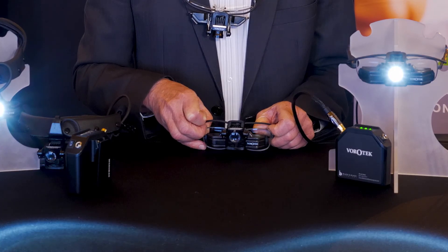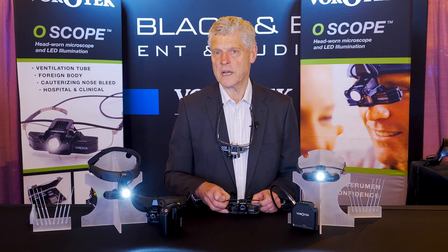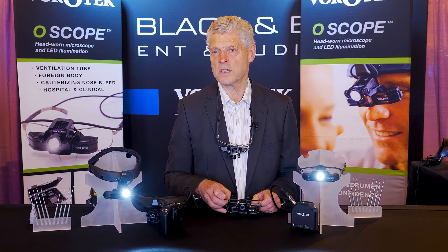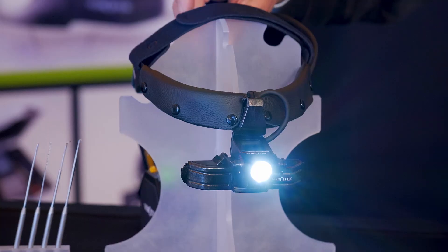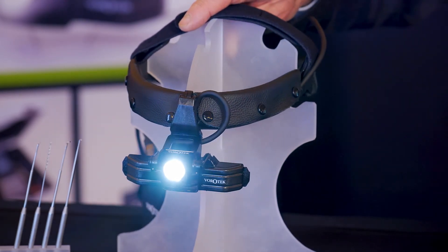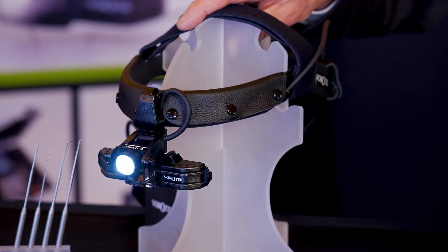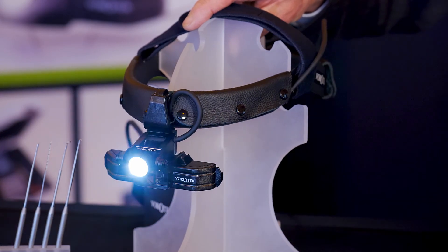It makes for a much more accurate and careful assessment. It is also very portable, so it's very easy to take it to other places in the hospital or anywhere else. Another appreciable advantage is the amount of time taken to perform examination and procedures — it is generally considerably quicker with an O-scope than with a microscope or a headlight. When there is any patient movement, a microscope will have to be repositioned and refocused, whereas with an O-scope the head can be moved much more quickly and, because of the big depth of field, there is almost no refocusing.